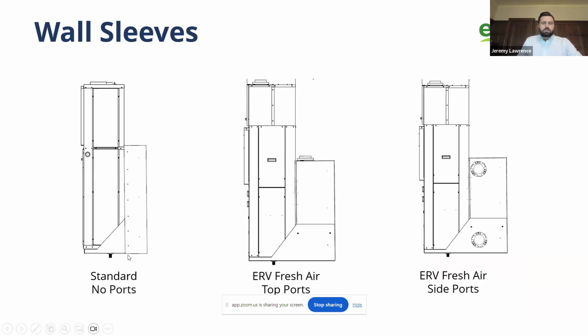So this slide is about the fresh air ports on the FreshPack ERV system. But one thing I want to point out is that as this unit is running in air conditioning mode, condensation is created, and the sleeve is actually the catch basin for any condensation created from air conditioning. And this is a 3/4 inch MIP fitting that sticks out of the bottom. So you would require a sanitary drain and a P-trap below this to catch that. Or if there's a floor drain, of course, that's good as well. And then you just connect your condensate line directly to the bottom of the sleeve.